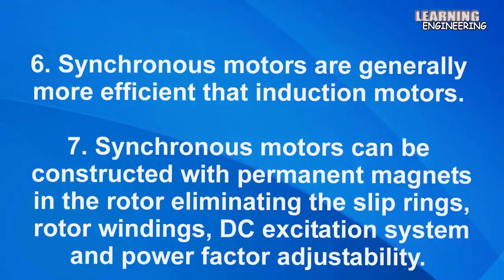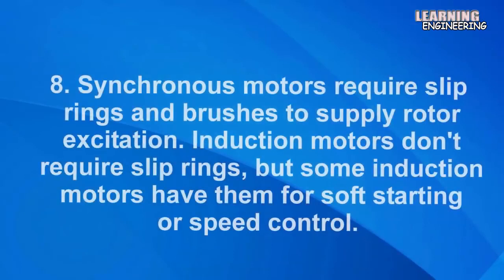Six, synchronous motors are generally more efficient than induction motors. Seven, synchronous motors can be constructed with permanent magnets in the rotor, eliminating the slip rings, rotor windings, DC excitation system, and power factor adjustability.